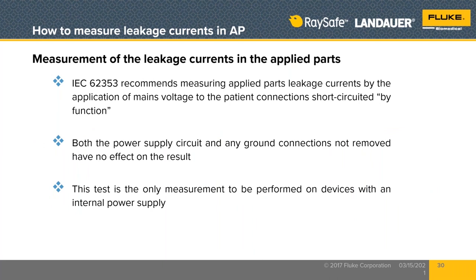So before we shift to the more specific slide deck about patient monitor testing, let's just review what we've learned. The IEC 62353 recommends measuring applied parts leakage currents by the application of mains voltage to the patient connections and having those connections all short-circuited by function. So ECG leads, we really mean by function, we mean applied part type. So applied parts like temperature sensors, thermistors that connect to the patient's skin, those are B type, those are grounded. And so we would test those with 100% of mains voltage applied when we do the test.